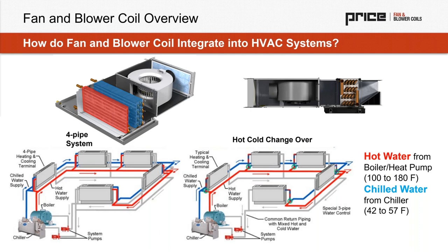Now, why would we choose each? Which one's more important? Which one should we use? The good news for fan coils, generally the decision doesn't have a lot of influence and weight to actual application and operation for the Boston market. In some cases, we do see specific choices for four-pipe systems in other markets, though, and that's really for the same reason we would see preheat or reheat on an air handler. If we have a draw-through makeup air style blower coil, we still do see in all markets a preheat configuration can help temper air during the colder months to make sure that the chilled water cooling coil wouldn't freeze. And we see that applied with fan coils in some cases as well.